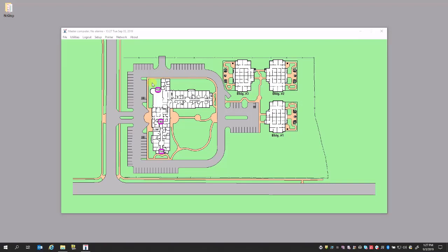The fails that you see here is that a transmitter was transmitted or tested or reset, and that the received transmission to these receivers are to a transmitter that is not programmed in the system. To fix this, that means that you have to learn in the transmitter using the subscriber database.